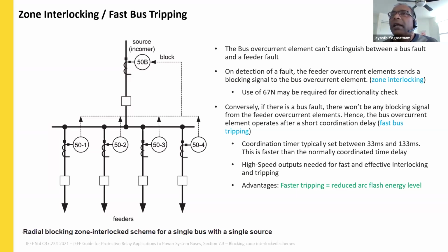In this case, the radial feeder will send a signal to block the protection operation of the source feeder, and in that way the fault will be taken care of by the relay on the radial feeder. That is called zone interlocking. Conversely, if there is a fault at the bus, that fault will be seen only by the source feeder relay, which immediately trips and isolates the fault. This has an advantage: the relays can act fast to clear the fault, and it also reduces the arc flash energy levels.